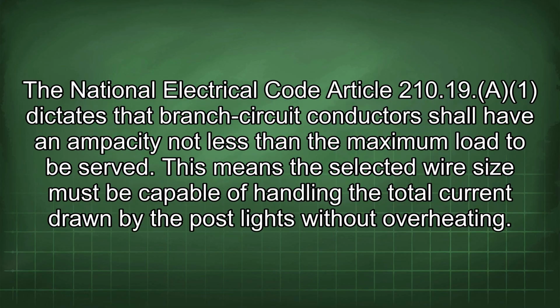The National Electrical Code Article 210.19(A)(1) dictates that branch circuit conductors shall have an ampacity not less than the maximum load to be served. This means the selected wire size must be capable of handling the total current drawn by the post lights without overheating.